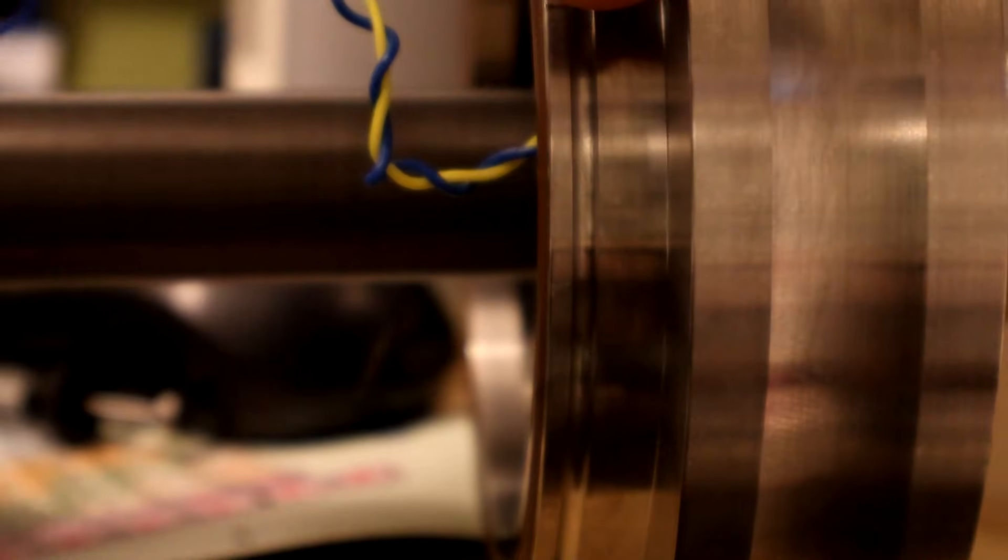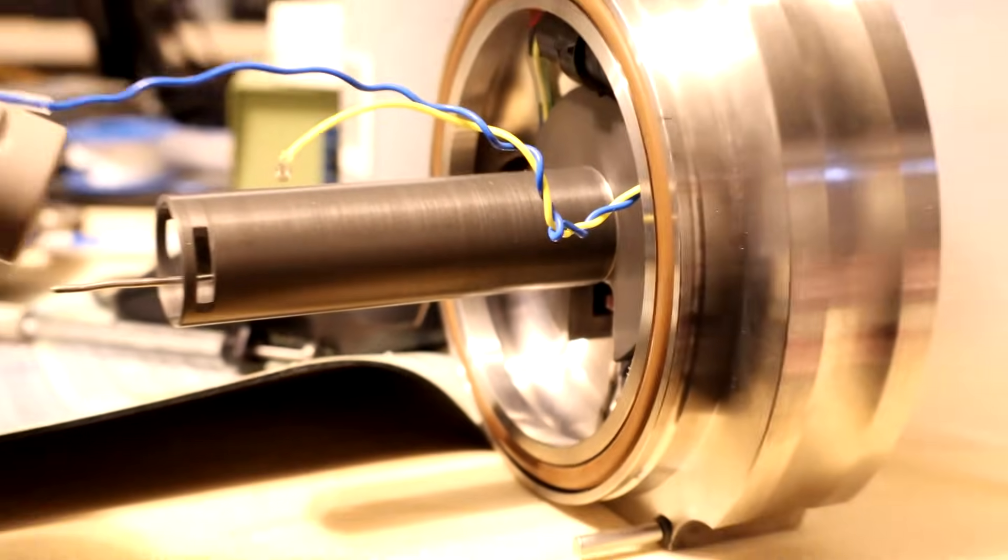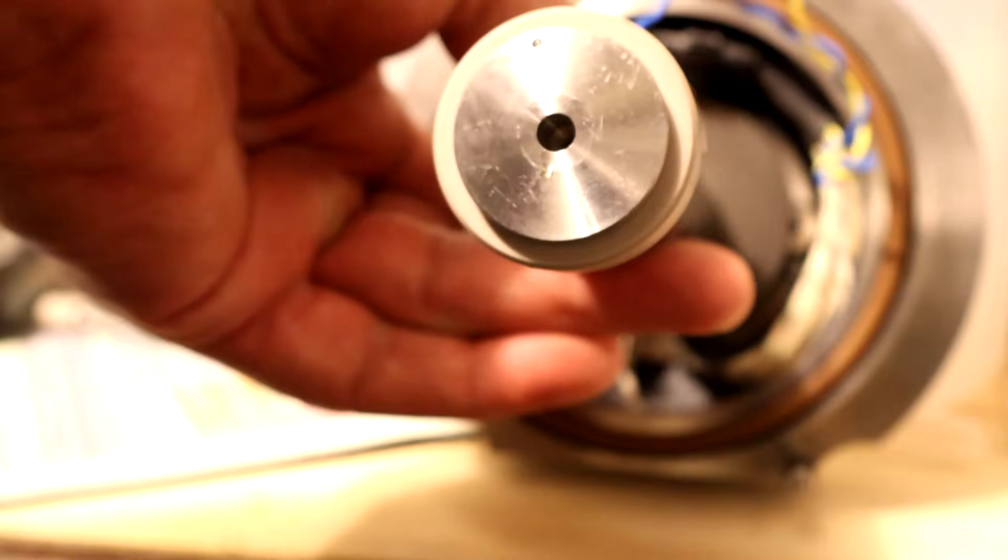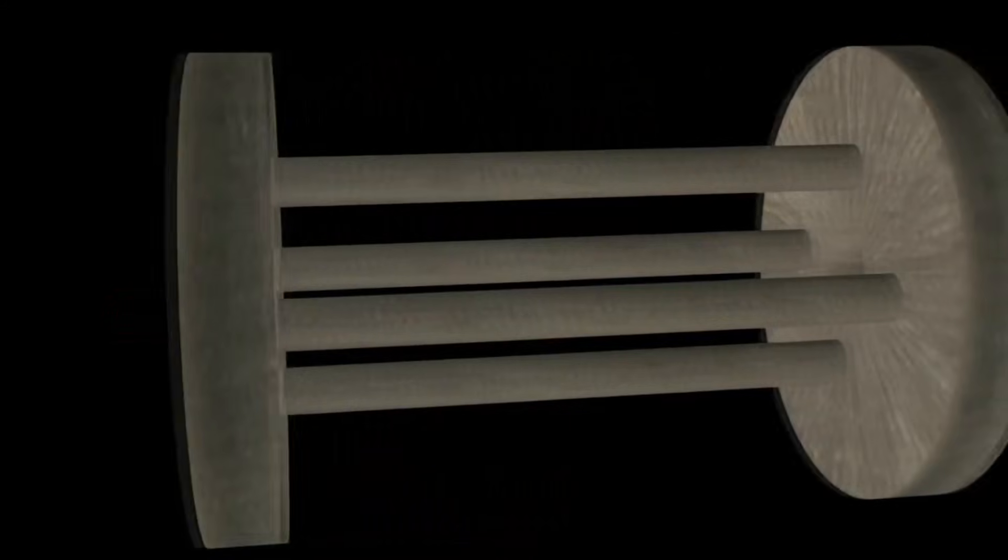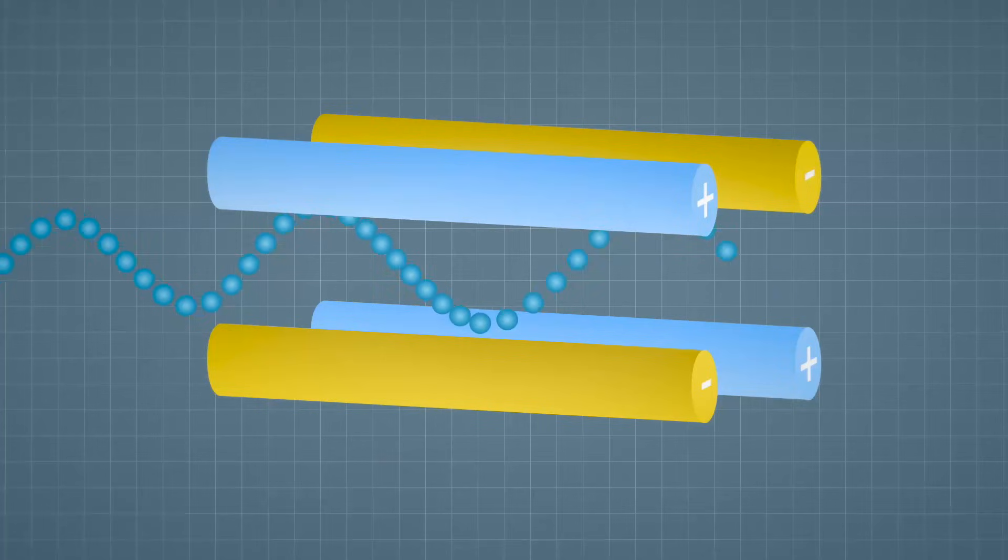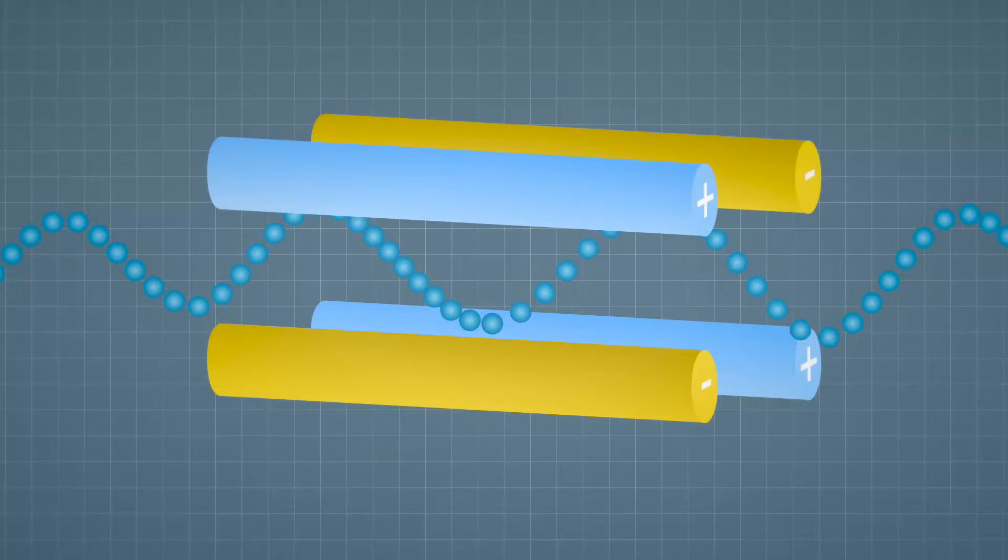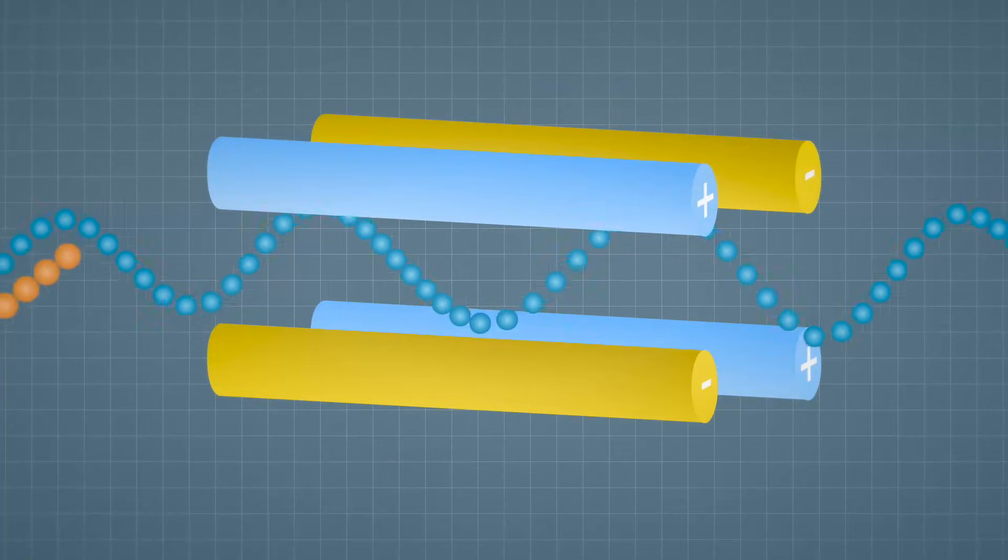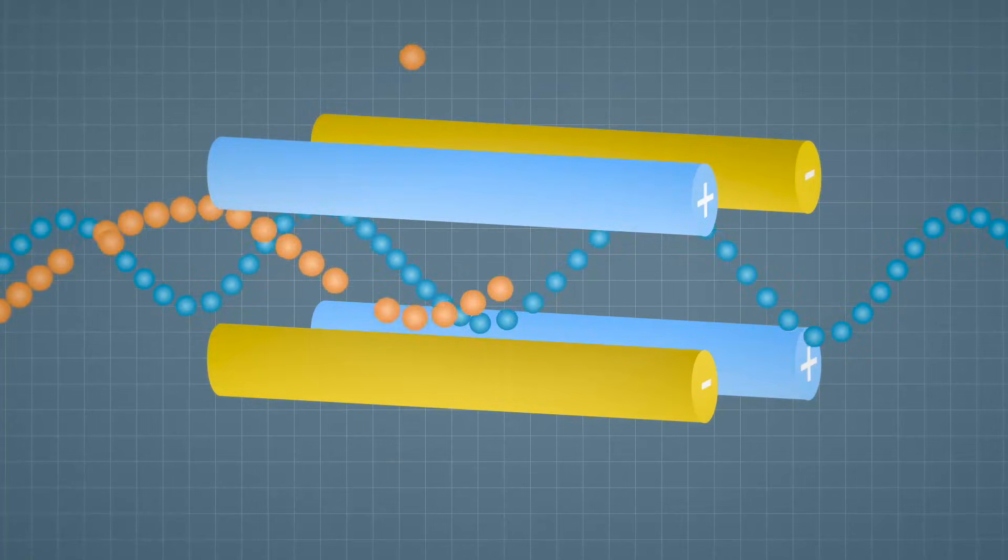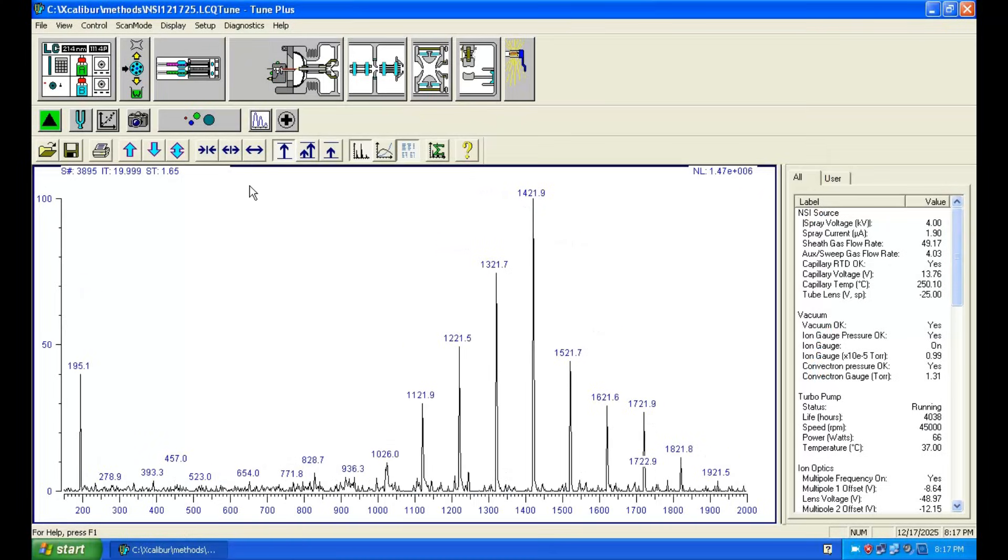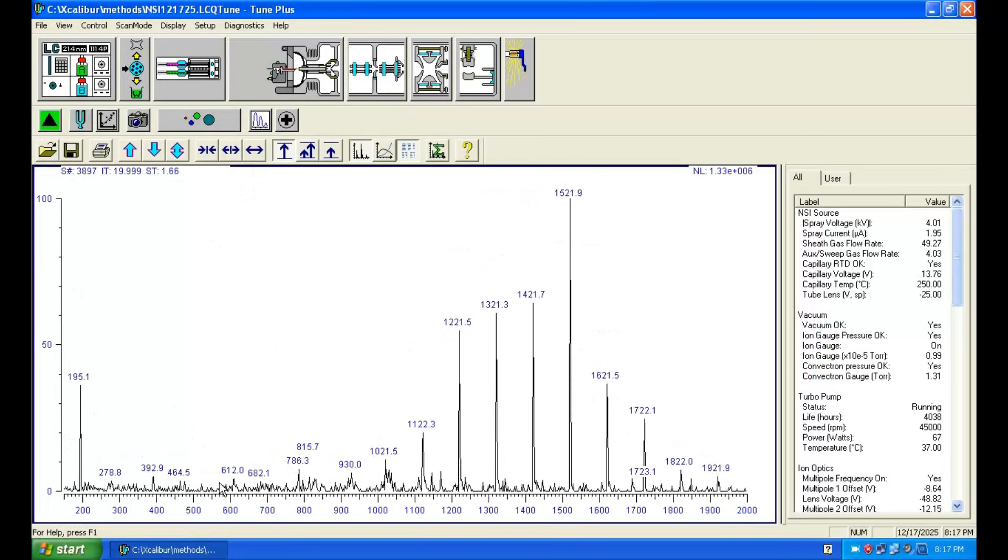Right on the inside, the pressure is in the low 10^-3 torr. The ion mean free path allows them to be accelerated towards the ion optic here before entering the first quadrupole. This quadrupole uses an arrangement of four rods under a DC and AC voltage at variable frequency. The electric field resulting from this setup allows for only one mass of ion to pass through. By changing the frequency and voltage, we can scan through a wide range of resonating mass-to-charge ratios and get a mass spectrum from low to high.